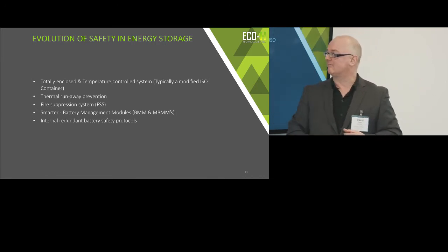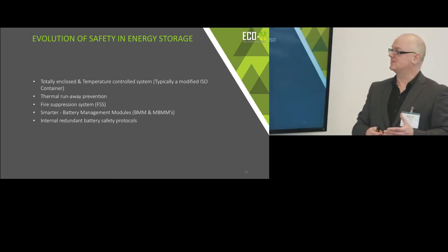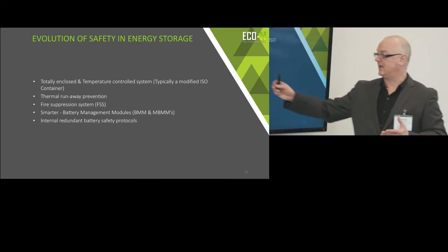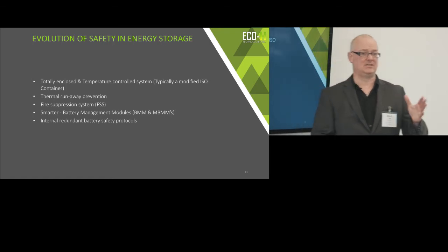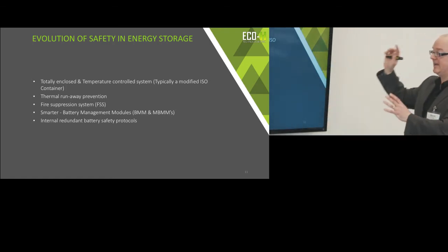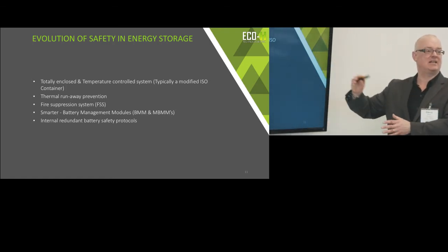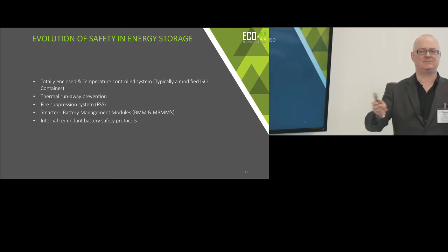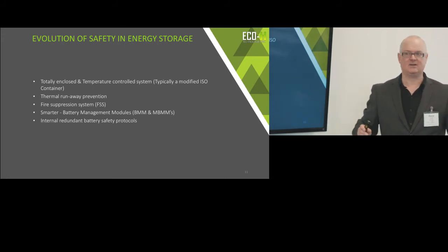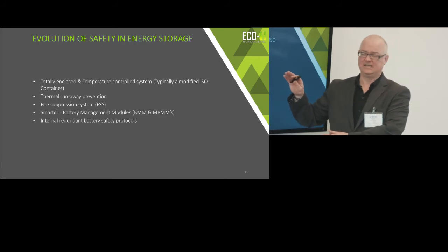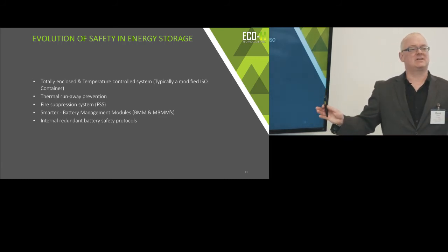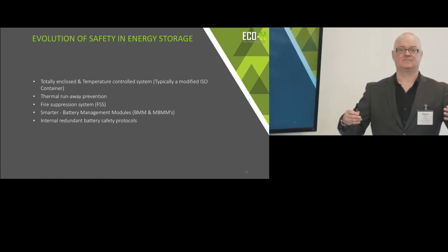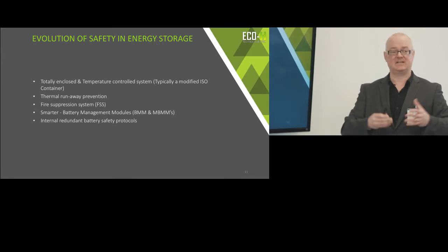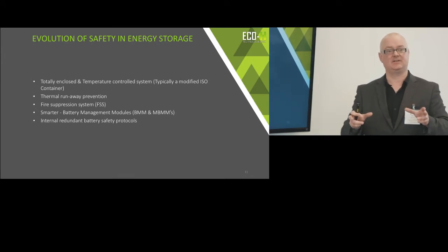So how do we prevent thermal runaway? There are a number of systems in place before you get anywhere near it. Firstly, all these batteries are in strings, in rack systems, typical 19-inch racks like you get in IT. All of this is in a standard ISO container with solid steel doors, kept shut, so if anything happens, it's contained inside that unit.